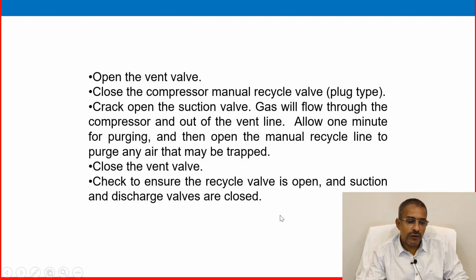Operation of the vent valve. Open the vent valve. Close the compressor manual recycle valve, plug type. Crack open the suction valve. Gas will flow through the compressor and out of the vent line. Allow 1 minute of purging and then open the manual recycle line to purge any air that may be trapped. Close the vent valve. Check to ensure the recycle valve is open and the suction and discharge valves are closed.